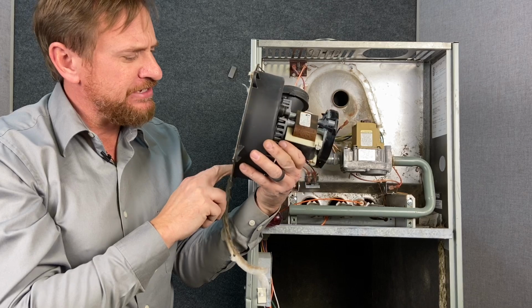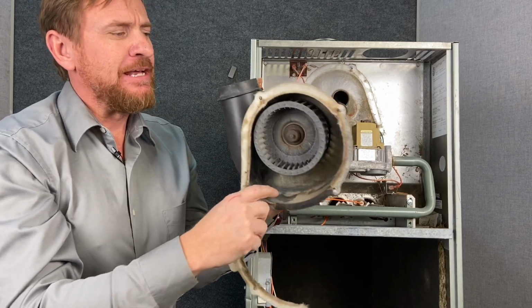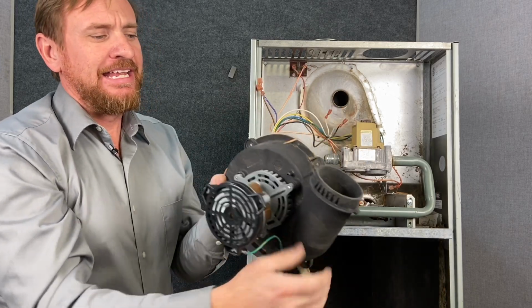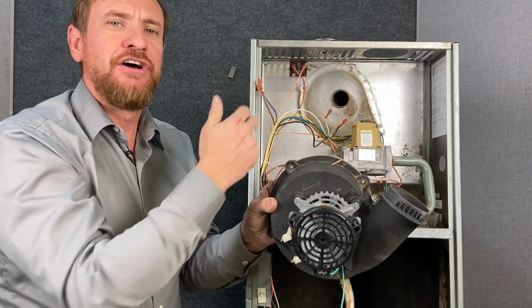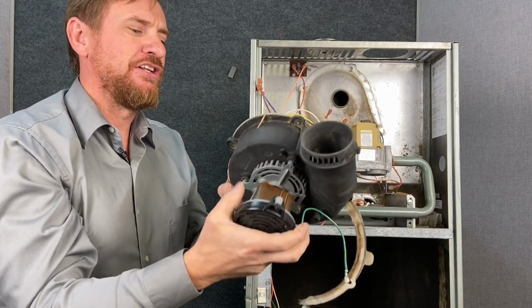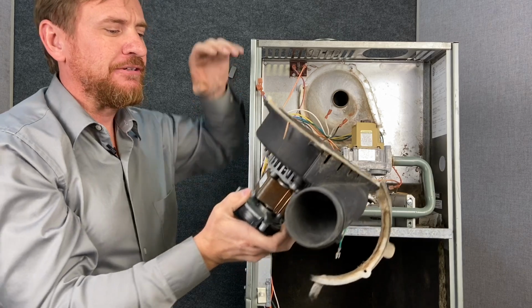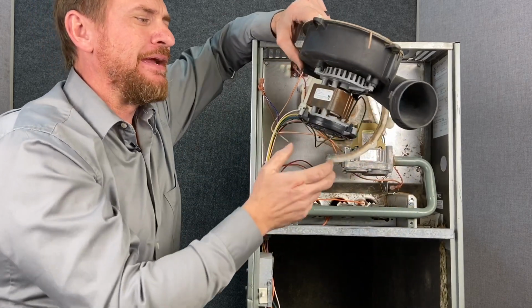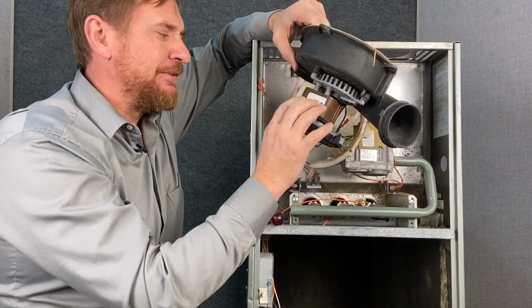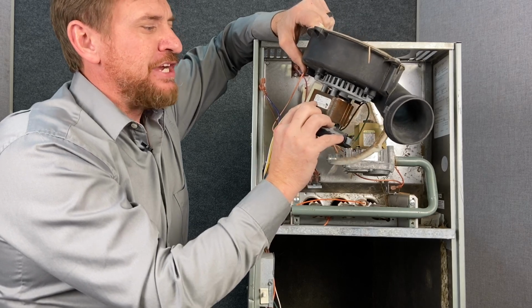On this particular one, it's not too much to worry about, but if you notice how that moisture is in there, how that can easily get through that hose, causing the hose to clog up or that pressure switch to clog up. But this is our inducer draft motor. One of the things we want to do when we're doing maintenance, other than listening to the sound of the bearings, we want to check the amp draw.